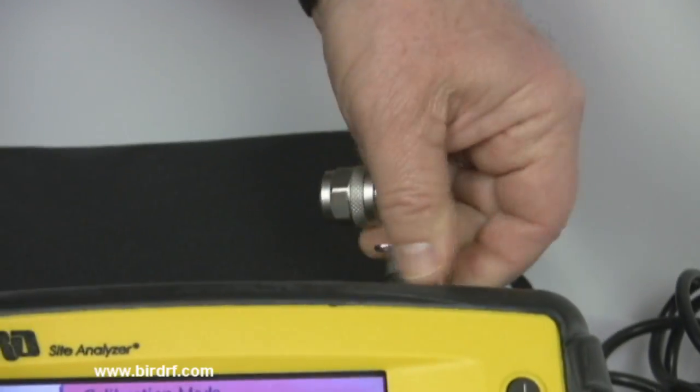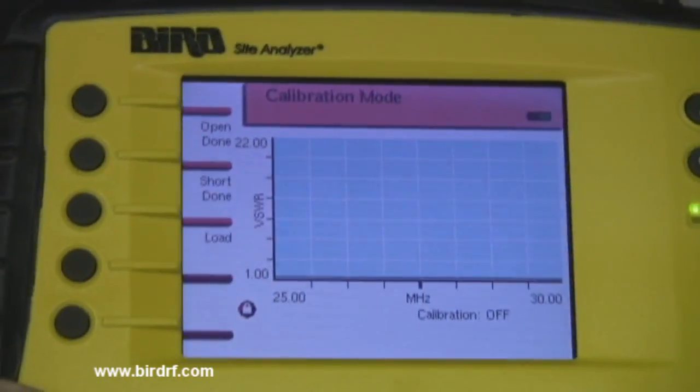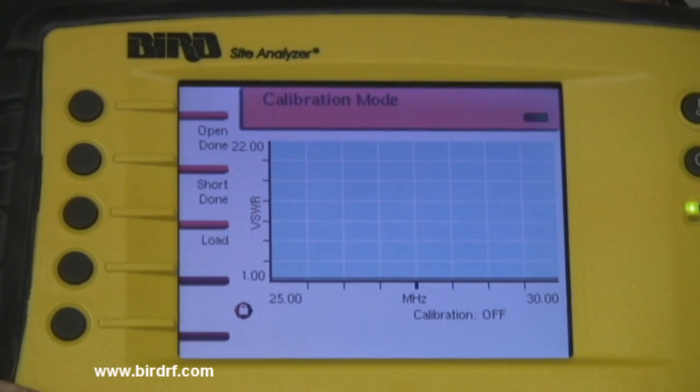The next step in the calibration process is the most important as we will set the dynamic range of the instrument. Attach the precision 50 ohm load connector to the cal combo test port of the SA.